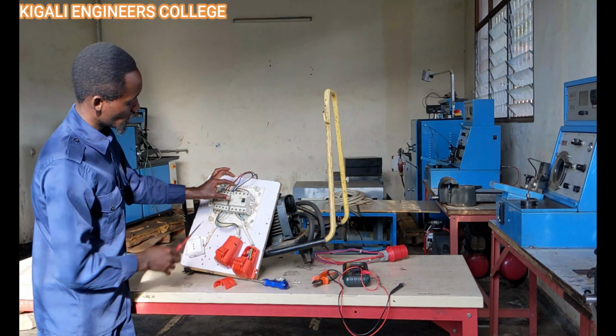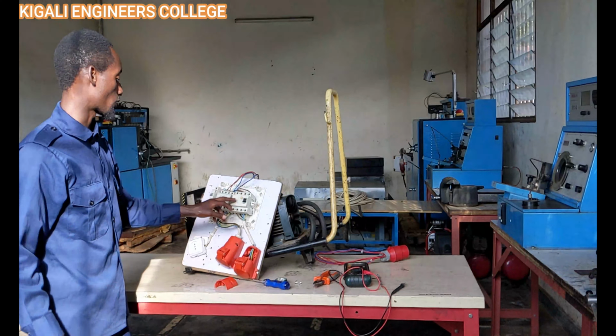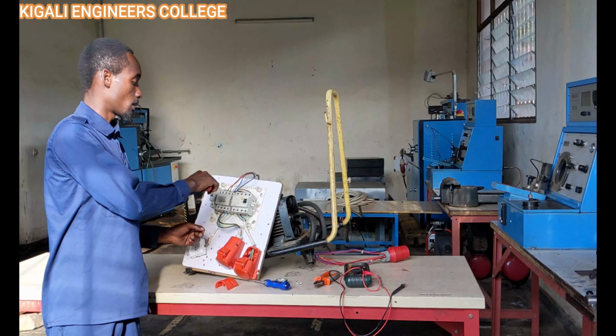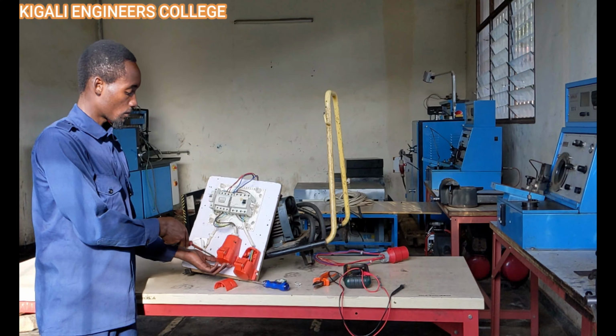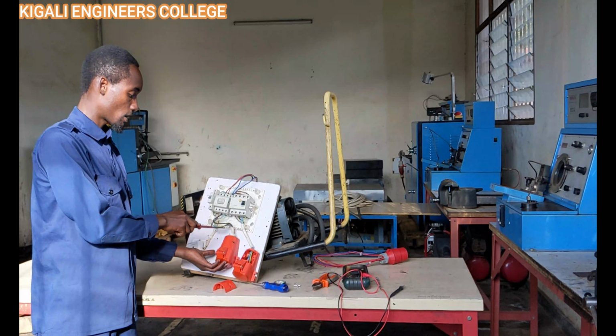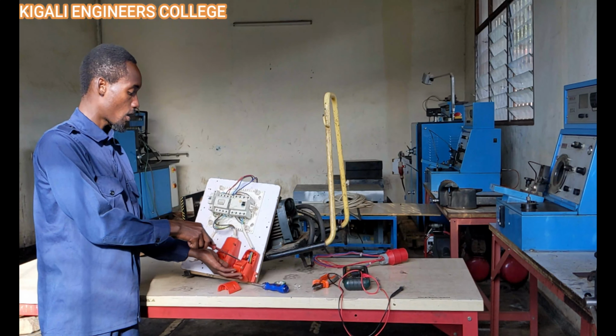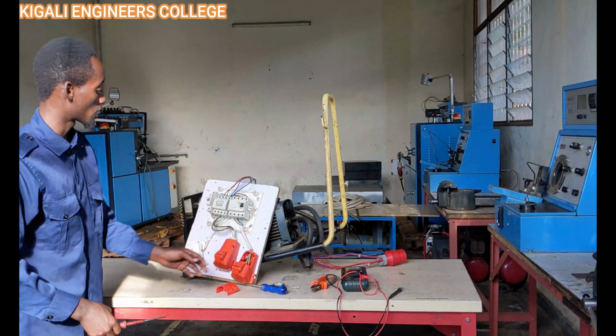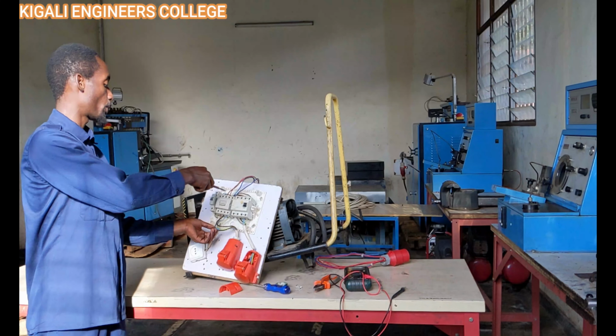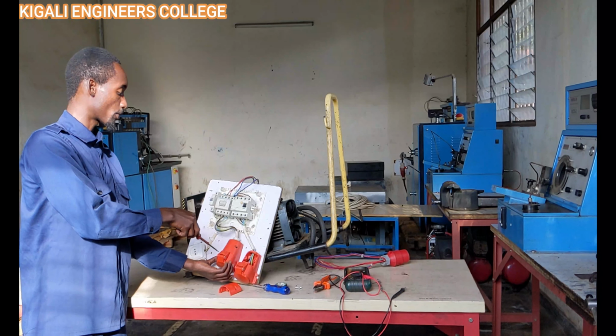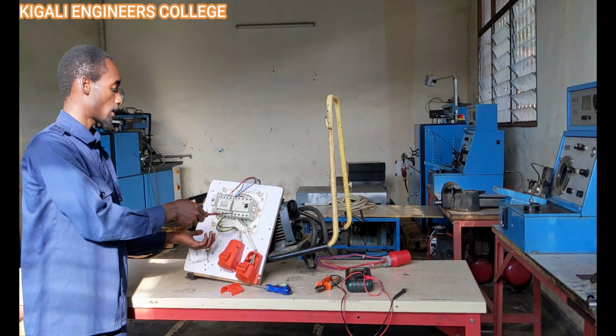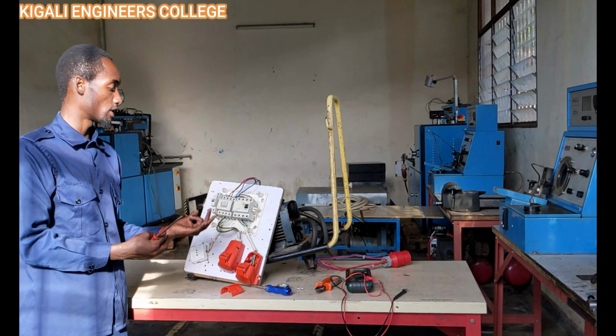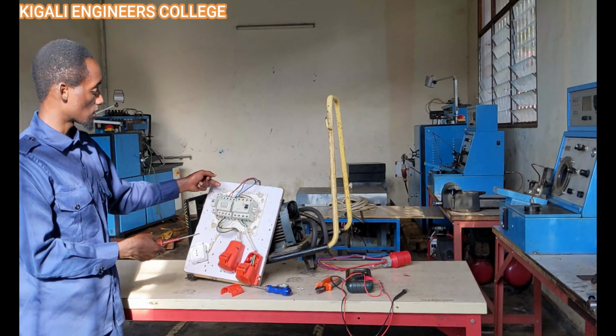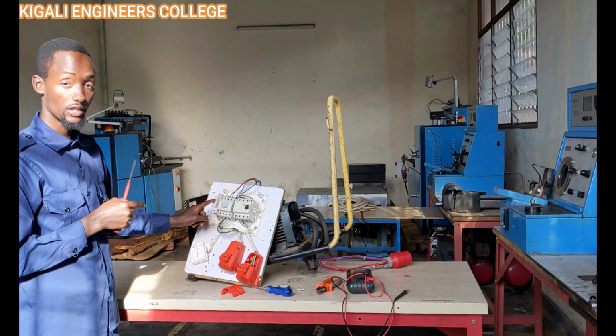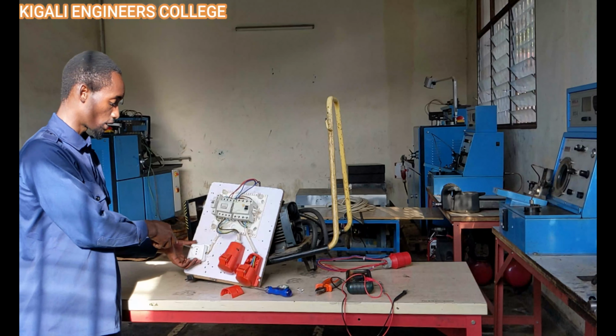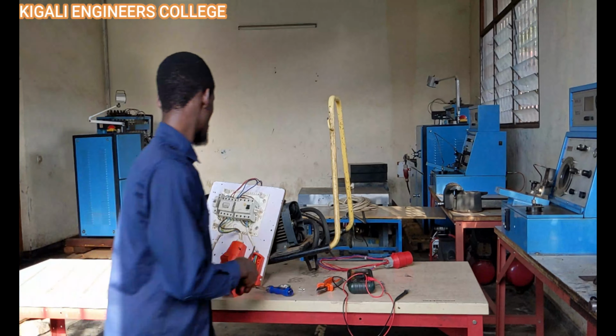Then the fifth one is the earth. As we see here, there is the three-phase circuit breaker connected, grouped in parallel. It means you will supply the three-phase either on this first three-phase socket outlet or on this second one. Because it is looped in parallel, whenever you supply here, this circuit breaker will get the three-phase voltage. It is also looped from one phase, which is a single phase that supplies and protects this one-phase socket outlet.